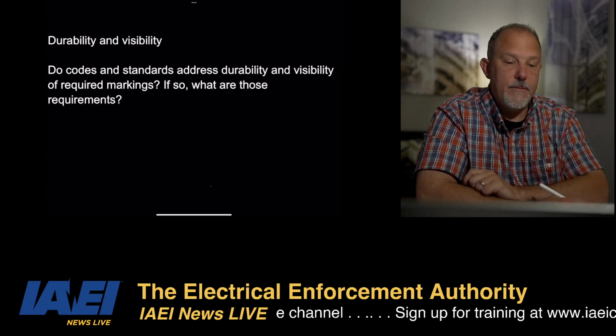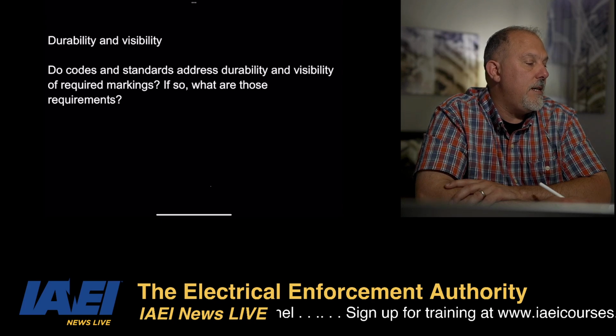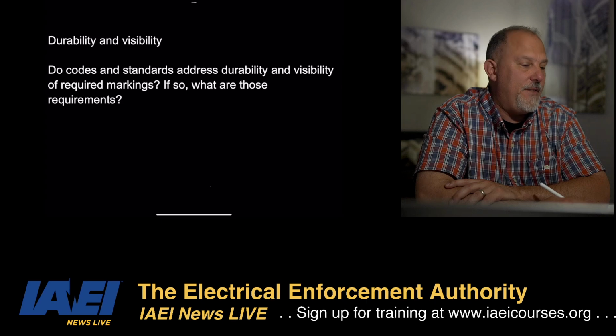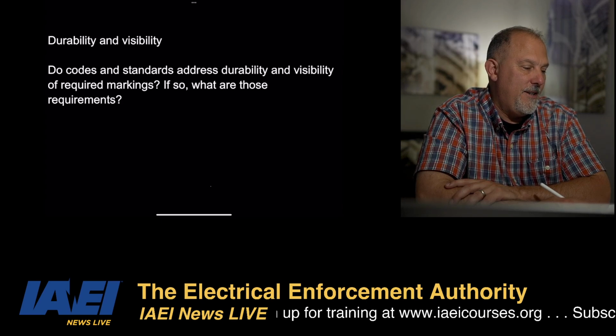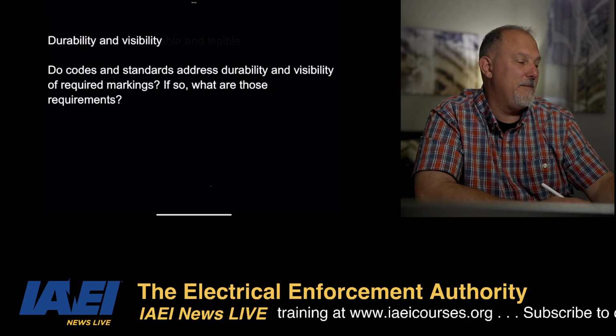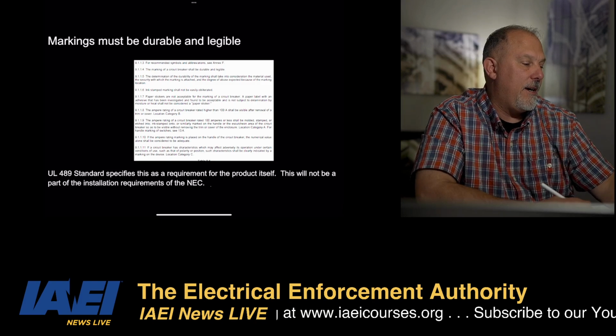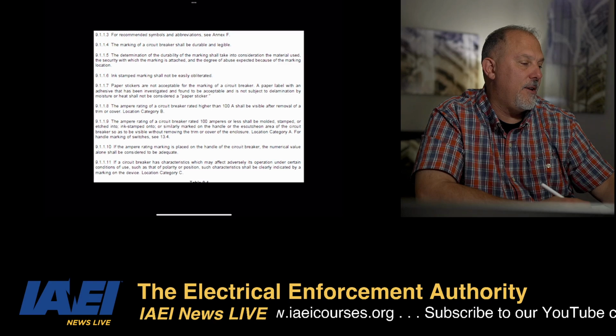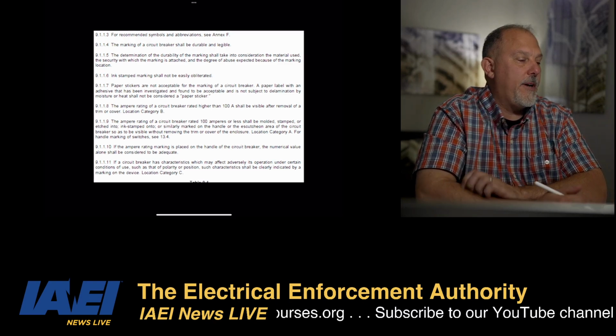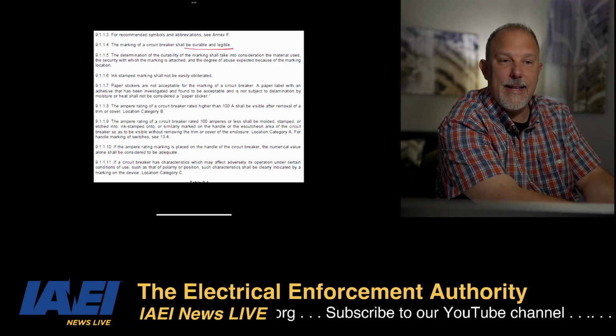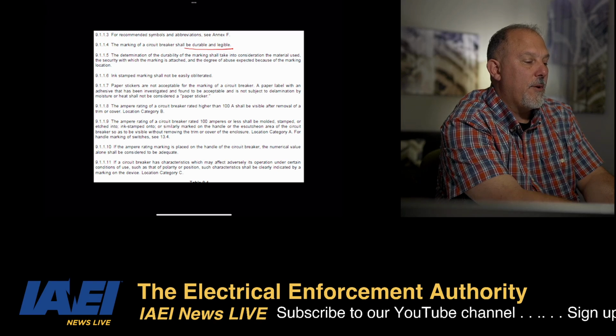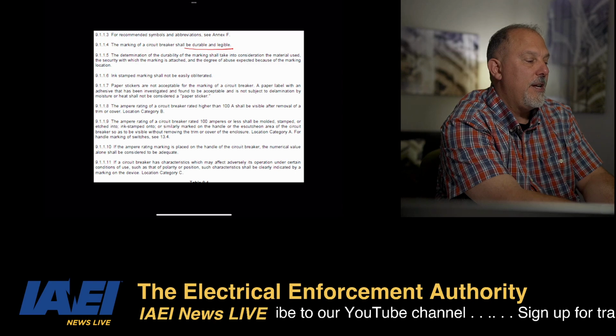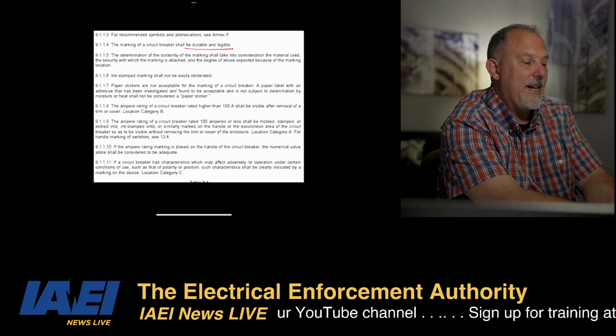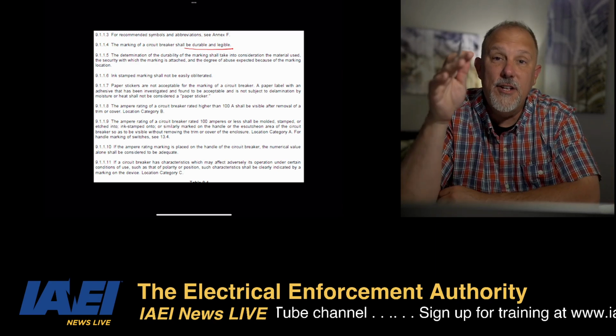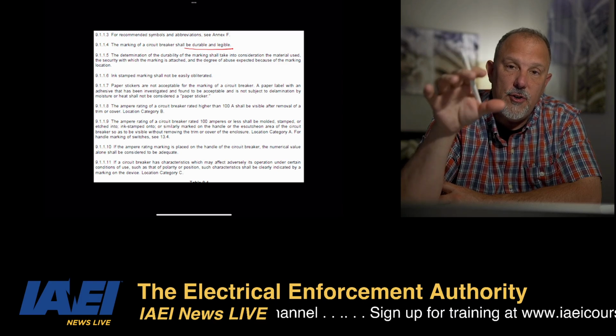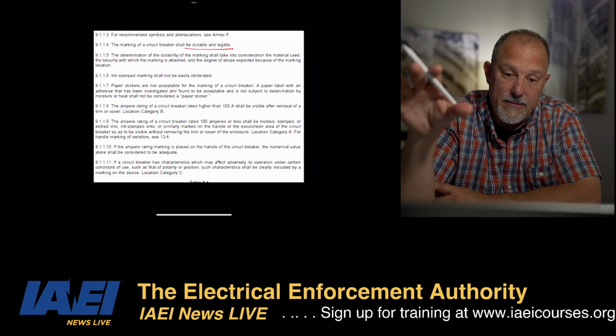Okay, now let's take a look at the next question. Do codes and standards address durability and visibility of required markings? If so, what are those requirements? All right, so let's take a look. The standard says the markings of circuit breakers shall be durable and legible. The determination of the durability of the marking shall take into consideration the material used, the security with which the marking is attached, and the degree of abuse expected because of the marking location. So you've got to think about it. Your markings could be just in a really bad spot, right?